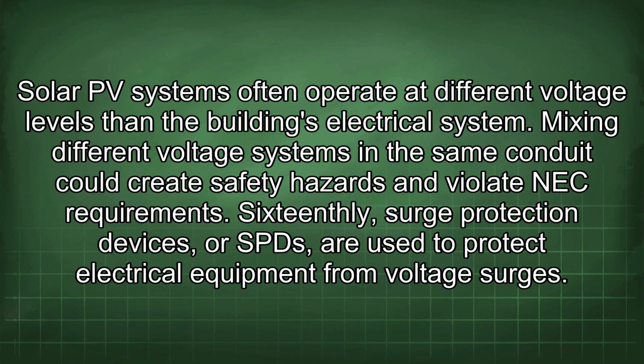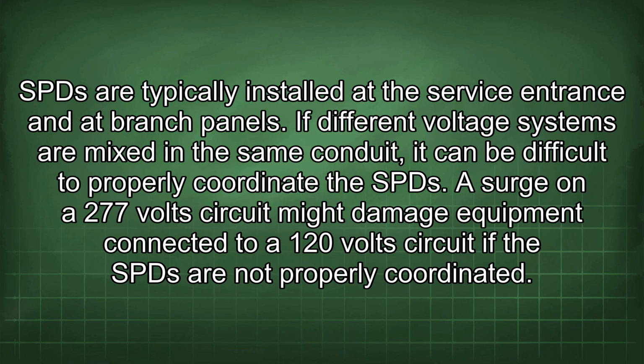16thly, surge protection devices, or SPDs, are used to protect electrical equipment from voltage surges. SPDs are typically installed at the service entrance and at branch panels. If different voltage systems are mixed in the same conduit, it can be difficult to properly coordinate the SPDs. A surge on a 277-volt circuit might damage equipment connected to a 120-volt circuit if the SPDs are not properly coordinated.